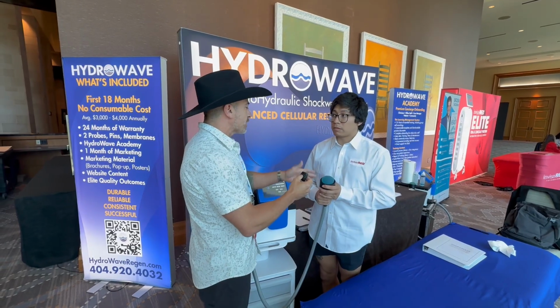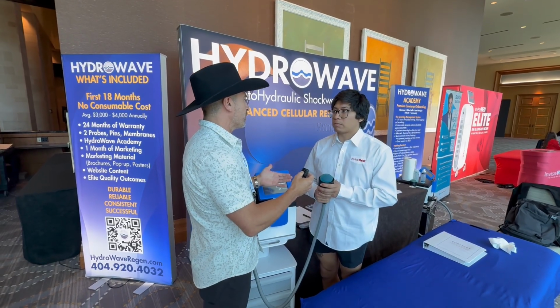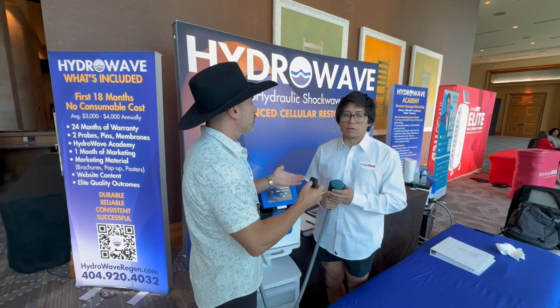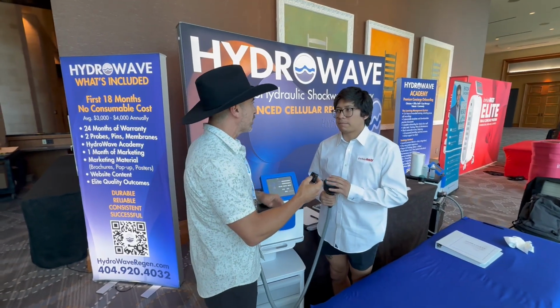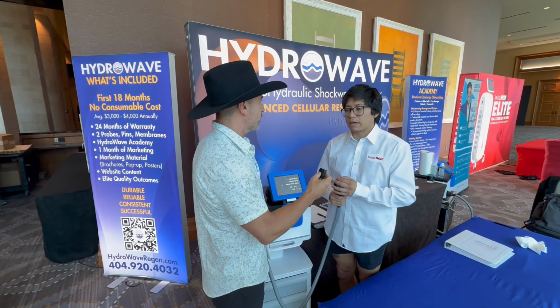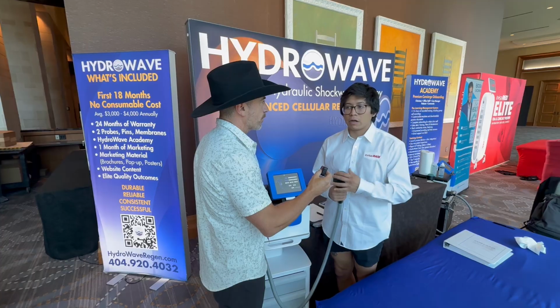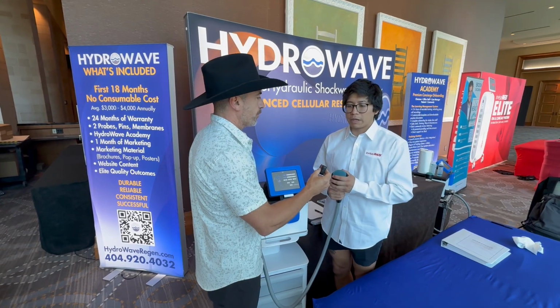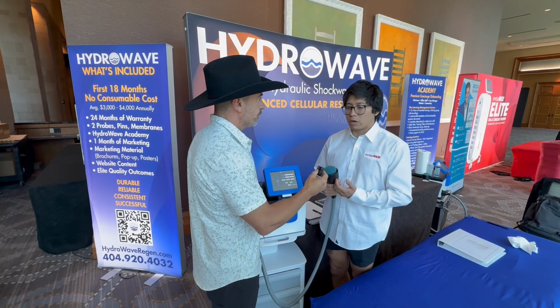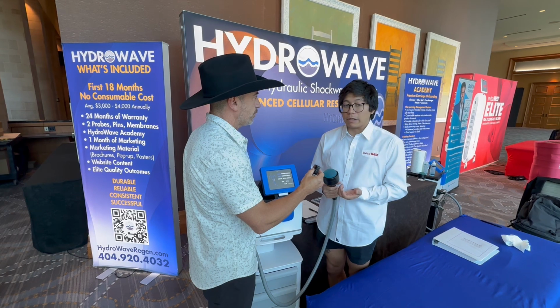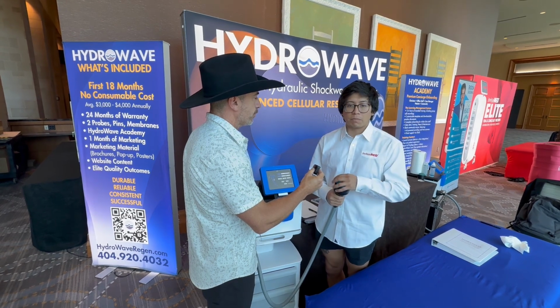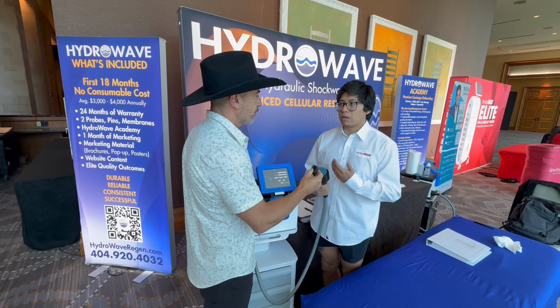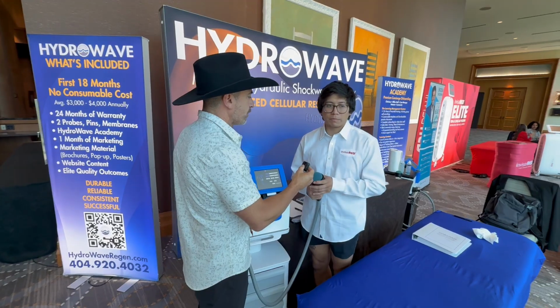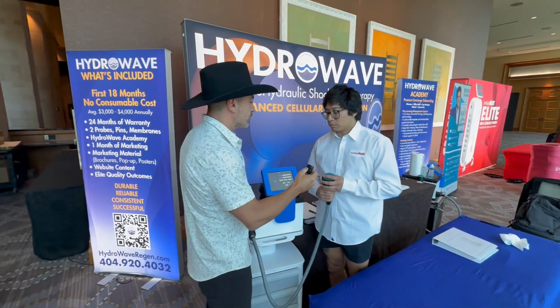And so basically with any of the membranes, it's mostly going to be if you did something, like you caused the leak. It's not like they just wear and tear on any of the devices. Exactly. Okay. Yeah, it's mostly user error, either mishandling or putting too much pressure in there, then putting it onto something sharp, or not taking jewelry off, which causes a rip or tear of the membrane. And then you brought something up about the consumables.